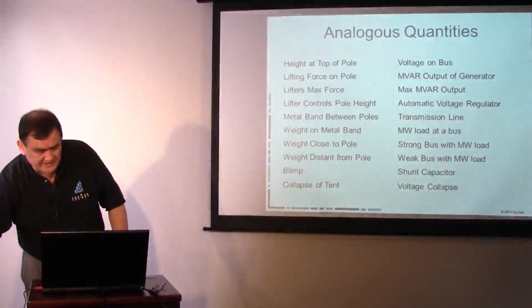Another way to look at it is you've got this huge tent. You've got your generators strategically placed around the circumference of this tent, and they're all keeping the tent with their poles at a certain height. And you really want them to all keep it at the exact same height. The lifting force on that pole in the upward direction is the megavar output of that generator. Once that generator hits its megavar limit, it can no longer nail that voltage, and that voltage will start to sag. As that voltage starts to sag, the other generators are going to have to pick up more megavars, just like the lifters adjacent to that one that's sagging are going to pick up more of the force.